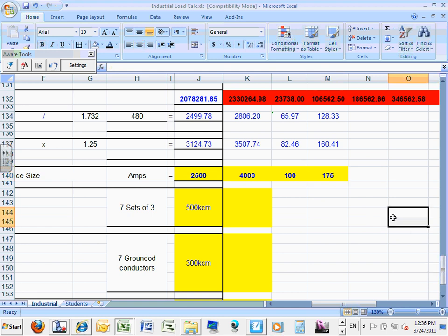Oh, hold on. Quick. It looks like they sized according to the... So most people parallel maybe 10, 12 sets? Yes, we're going to do it. Now, do you guys want me to size the switch for you here? To size the cable here for you? No, I want you to do the math. Right here, you did the switch here. Yep, and you copied and pasted it over to the receptacle panel, and I changed the voltage to 208.